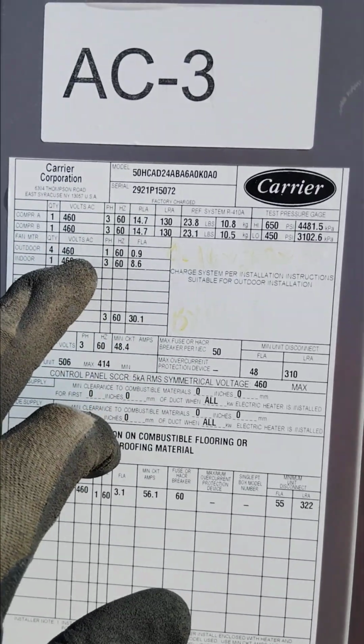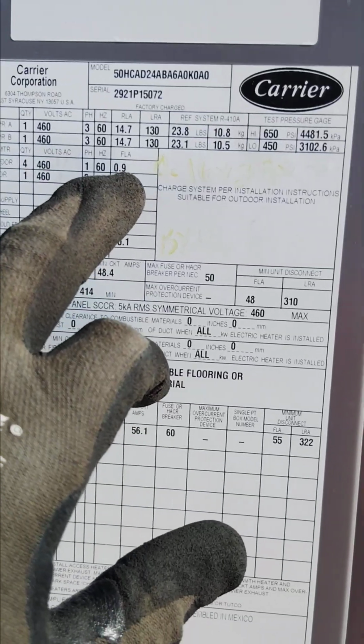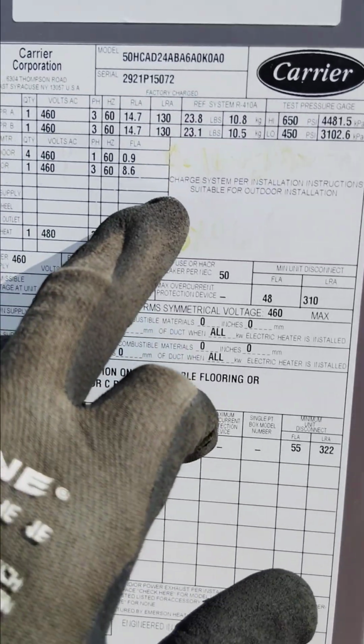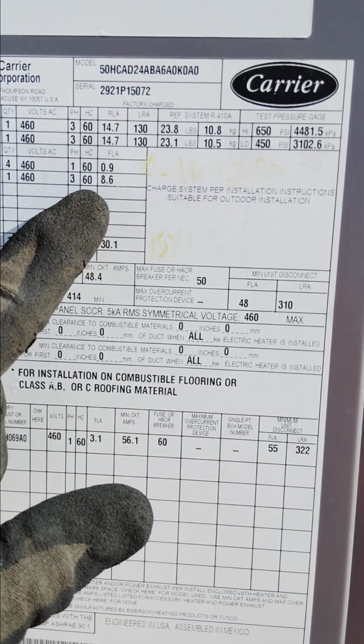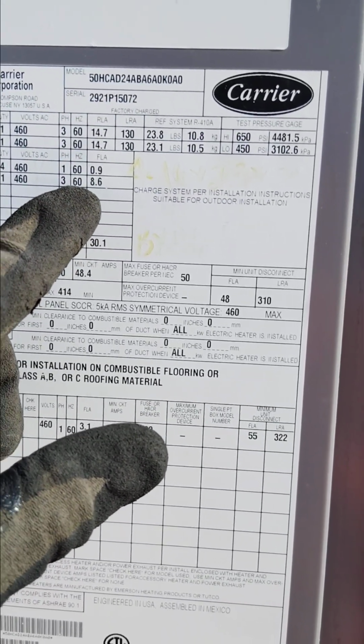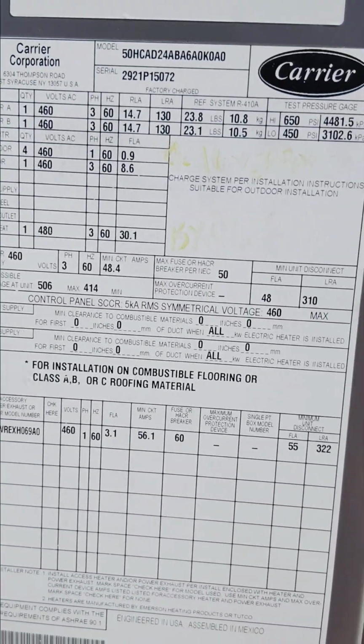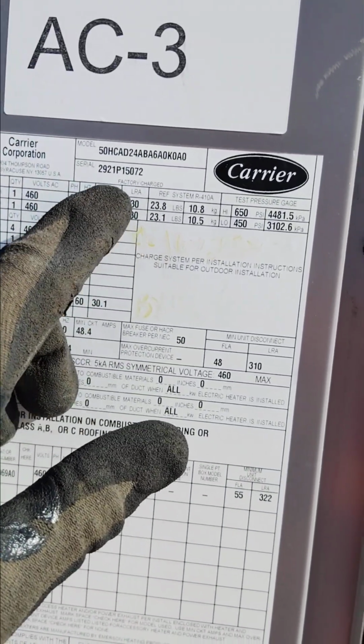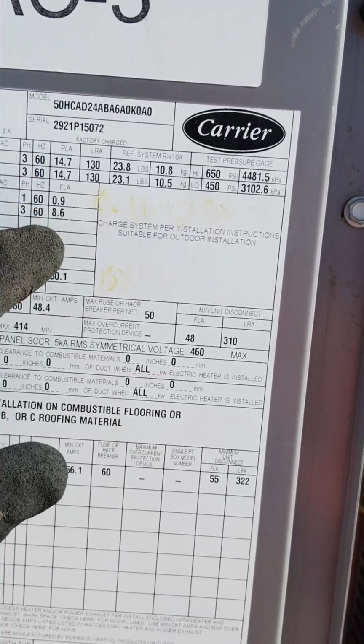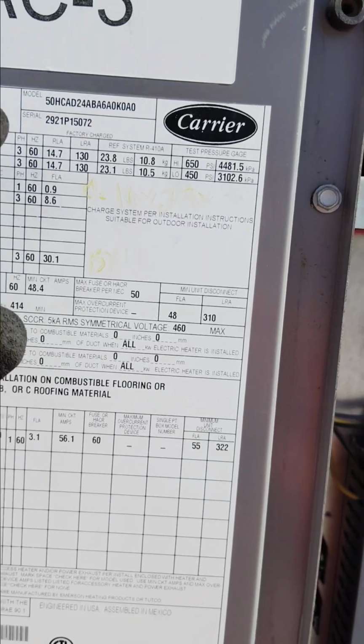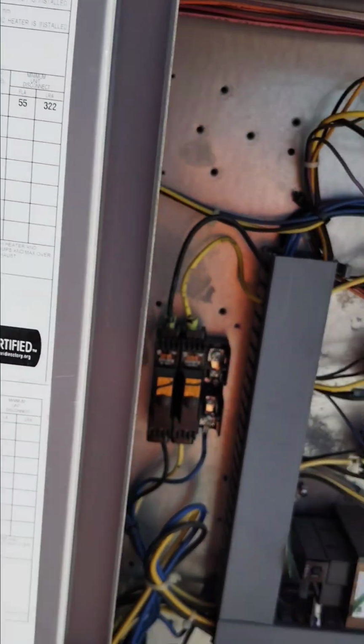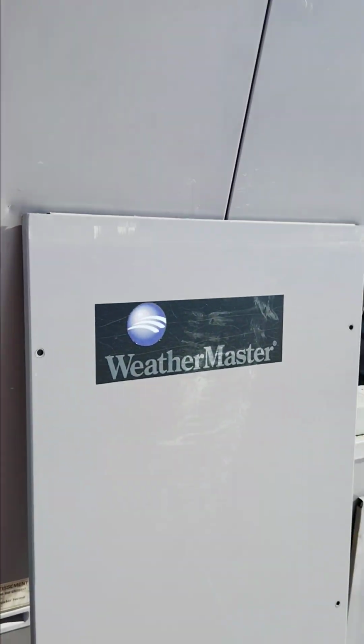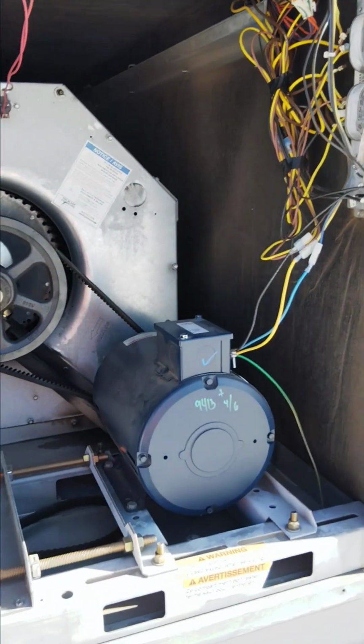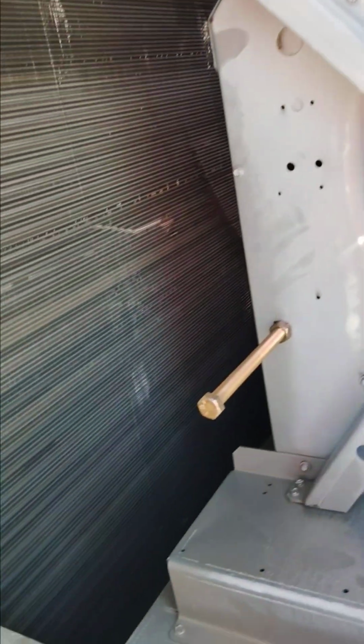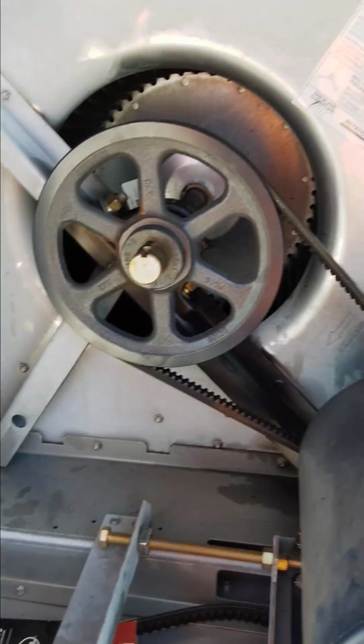The outdoor motors are single phase, but it's still 460, so it's high voltage, and it's 0.9 amps per fan, not too much. The indoor is a 3-phase motor, and the amperage on that would be like 8.6. So when we're doing the PM, we double check the amperage going through each wire, going to each component, to make sure everything is within specs. We check all of that, check the temperature on the inside, and make sure we at least have a 20 degree delta T between the indoor and the outdoor temperature, and that's it.